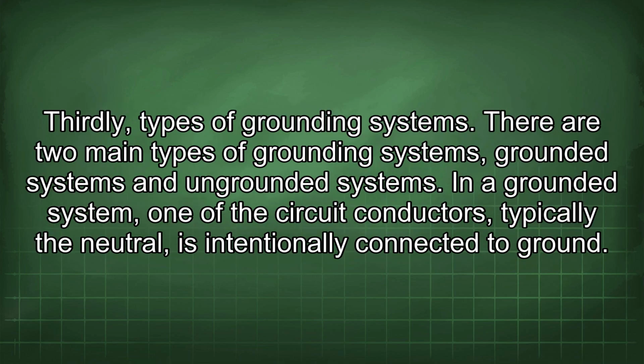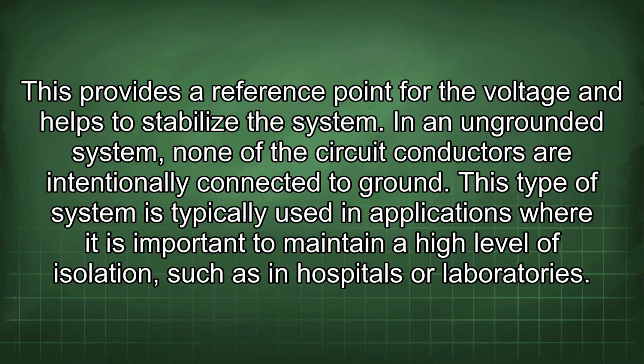Thirdly, types of grounding systems. There are two main types of grounding systems: grounded systems and ungrounded systems. In a grounded system, one of the circuit conductors, typically the neutral, is intentionally connected to ground. This provides a reference point for the voltage and helps to stabilize the system. In an ungrounded system, none of the circuit conductors are intentionally connected to ground. This type of system is typically used in applications where it is important to maintain a high level of isolation, such as in hospitals or laboratories.